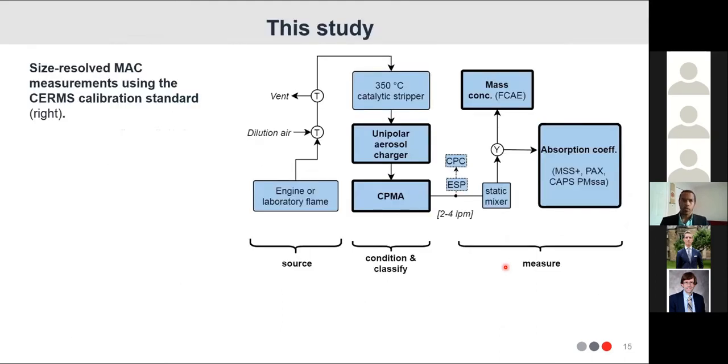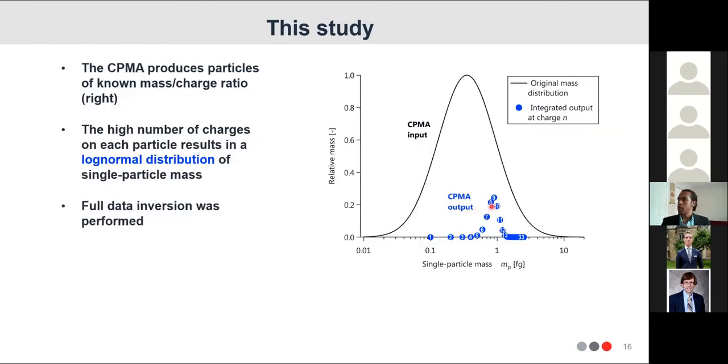So in this study, we're going to report results from the CERMS, the CPMA electrometer reference mass standard. This is normally used for calibration, but in this study, we use it and interpret the results in terms of MAC. We have a few different sources, so this is simplified here because the setup varied. We use the CPMA electrometer to charge particles and select them by mass-to-charge ratio, and then measure the mass concentration coming out and the absorption coefficient after the CPMA. The key detail of this setup is that we use a unipolar charger, which is a corona charger, which gives us an extremely high number of charges per particle, and because of those high number of charges per particle, we actually end up with something like a log-normal distribution coming out of the CPMA. So we can use the mean or the mode CPMA mass, output mass, to represent the single particle mass of the particles coming out. We don't have to worry about multiple charge correction. It's built into our setup.